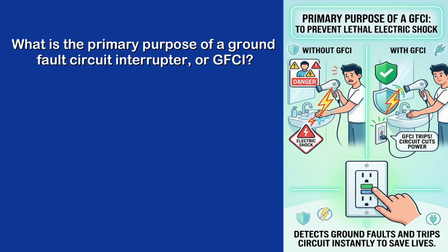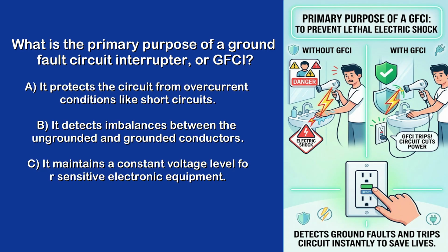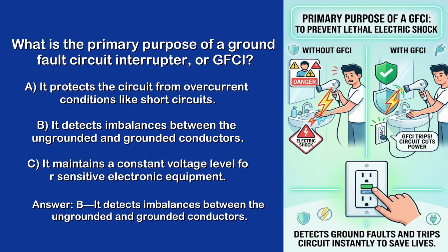Question 2. What is the primary purpose of a ground fault circuit interrupter, or GFCI? A. It protects the circuit from overcurrent conditions like short circuits. B. It detects imbalances between the ungrounded and grounded conductors. C. It maintains a constant voltage level for sensitive electronic equipment. The answer is B, it detects imbalances between the ungrounded and grounded conductors.